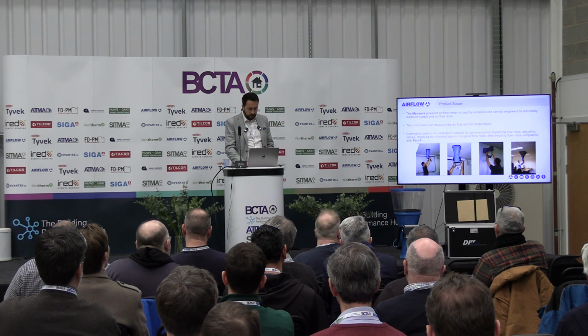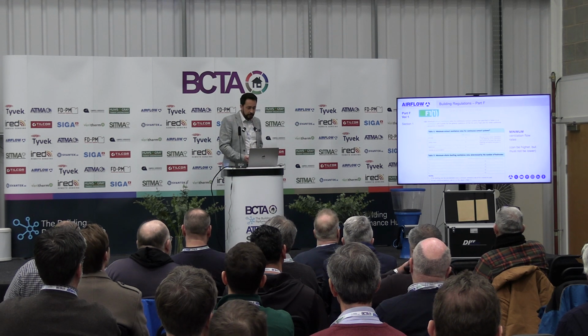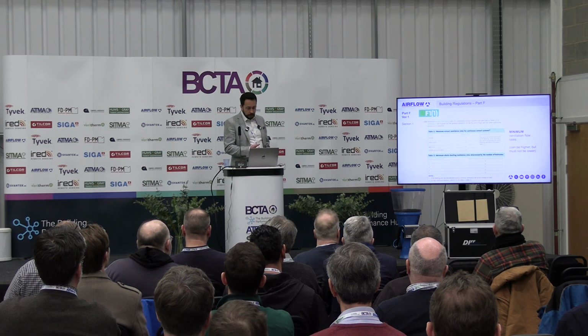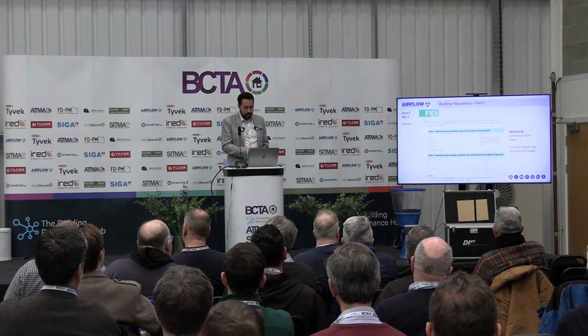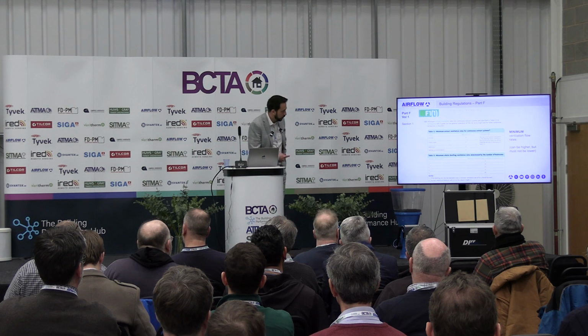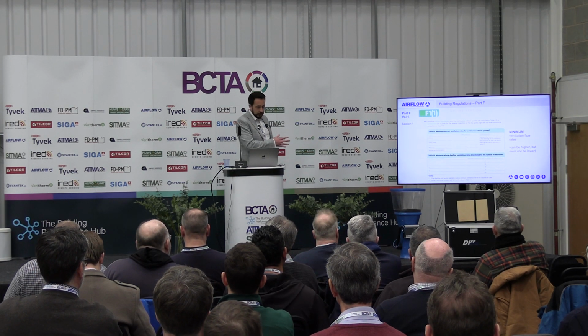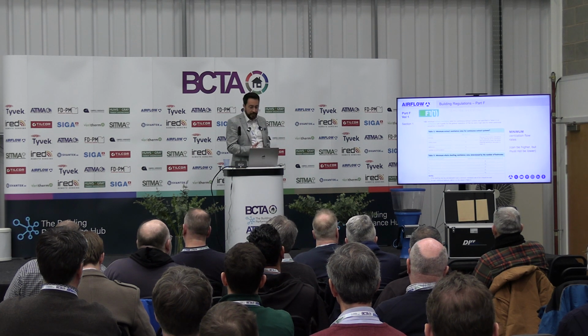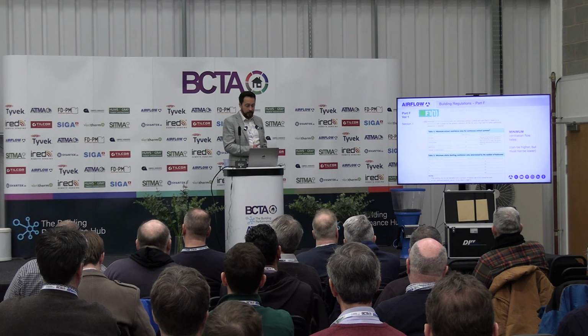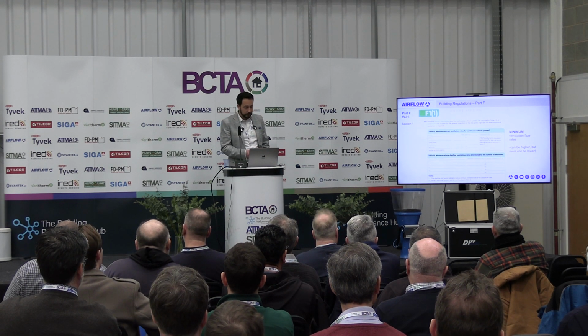Volume 1 is for dwellings. And in Volume 1, Part F, Section 1, it's got a couple of tables here, Table 1.2 and Table 1.3. You may just be able to make out some of those figures, some of you at the front, but in this table, it's minimum ventilation flow rates. So they can be higher, but they can't be lower than that, otherwise it fails the building regulations.